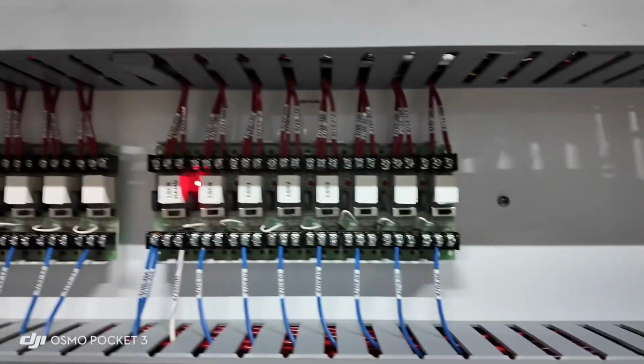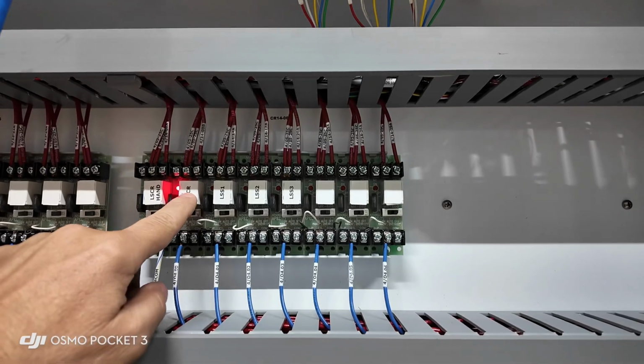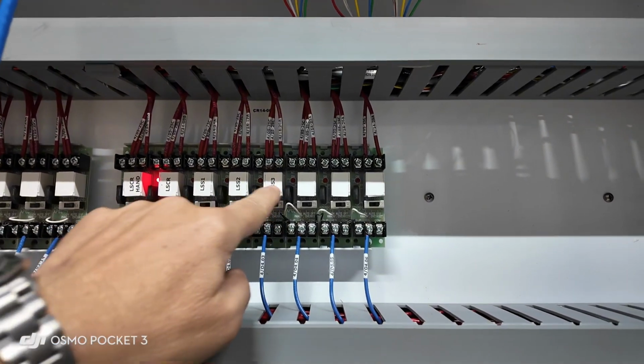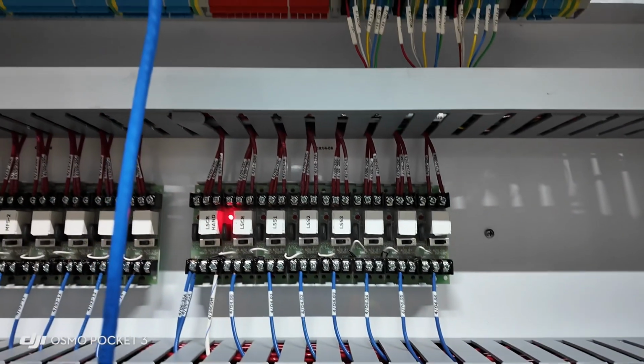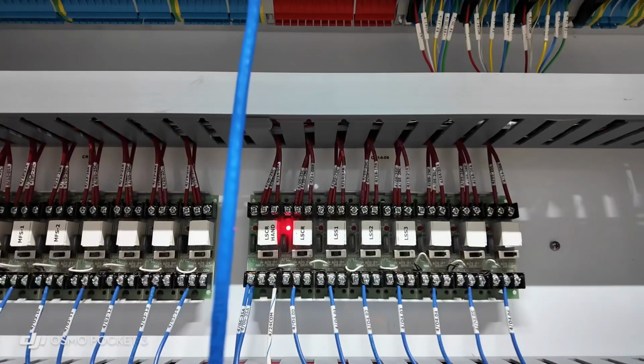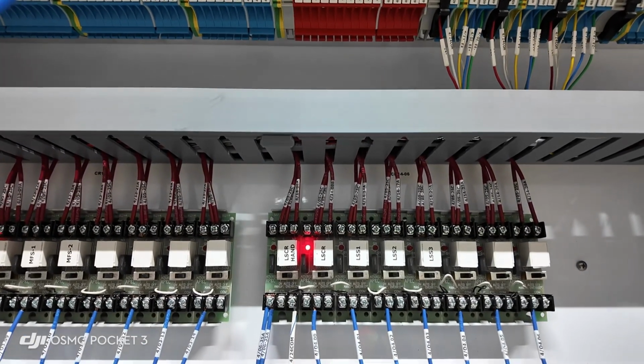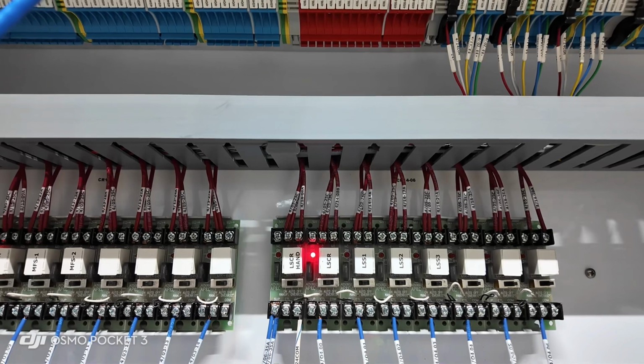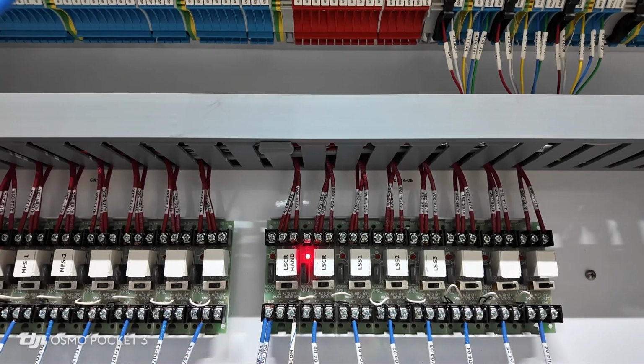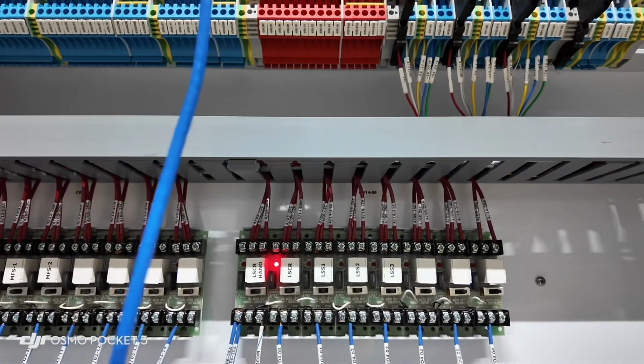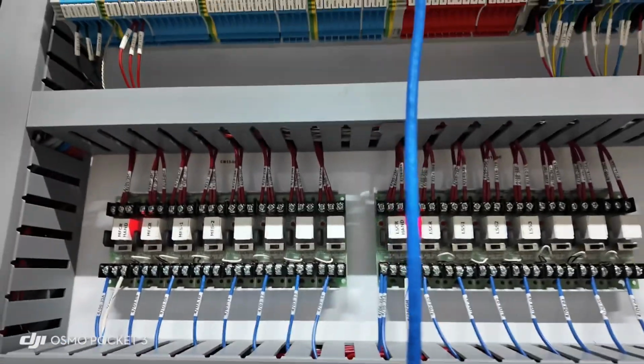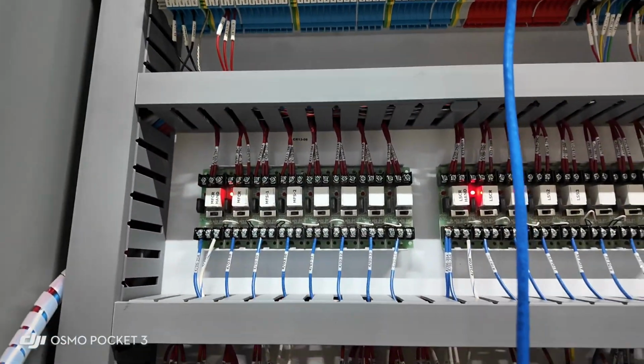We have the same thing for our other solenoids, which are our liquid stop valve solenoids that are in front of our motorized metering valves. Same thing occurs there. There's a liquid stop control relay and a liquid stop control relay hand mode, which allows us to operate it without a PLC to get those solenoids on.